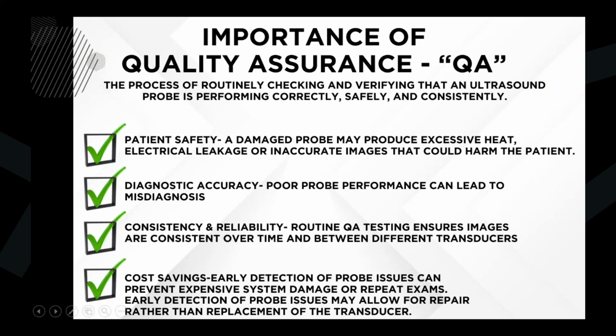Routine quality assurance testing ensures images are consistent over time and between different transducers, and can be effective in cost savings. Early detection of probe issues can prevent expensive system damage or repeat exams. Early detection of probe issues may allow for a repair rather than the replacement of the transducers.